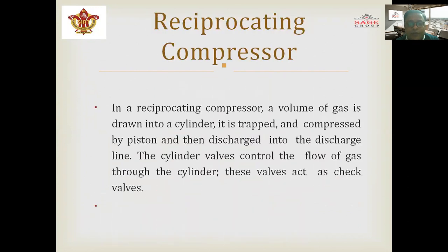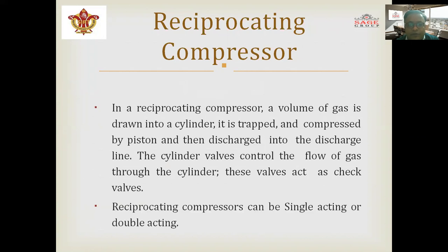In a reciprocating compressor, a volume of gas is drawn into the cylinder, trapped and compressed by the piston, and discharged into the discharge line. The cylinder valve controls the flow of gas through the cylinder and acts as a check valve. It can be single-acting or double-acting. When air compresses from one side, it is single-acting; from both sides, it is double-acting.